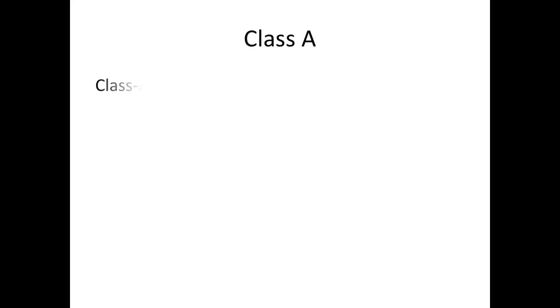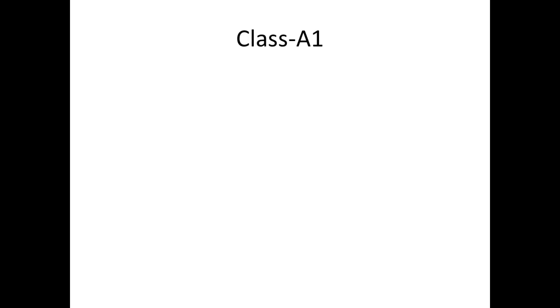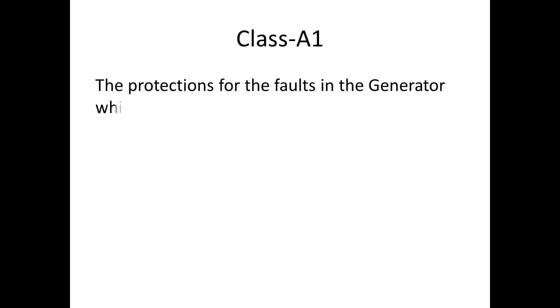First, I am going to see Class A tripping. Class A tripping is further subdivided into Class A1 and Class A2. In Class A1 tripping, the protection is for faults in the generator which need immediate isolation of the generator.